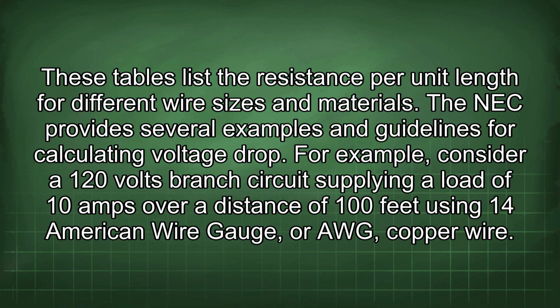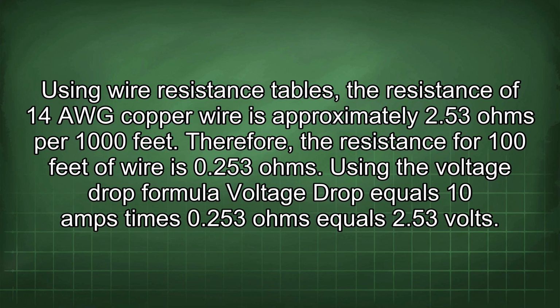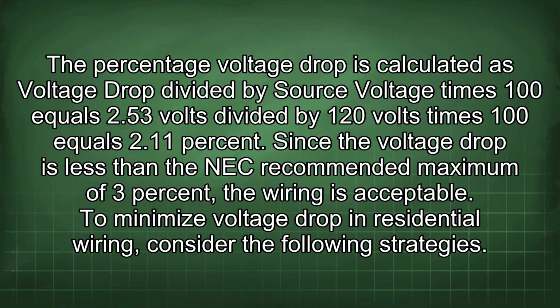For example, consider a 120 volt branch circuit supplying a load of 10 amps over a distance of 100 feet using 14 American Wire Gauge, or AWG, copper wire. Using wire resistance tables, the resistance of 14 AWG copper wire is approximately 2.53 ohms per 1000 feet. Therefore, the resistance for 100 feet of wire is 0.253 ohms. Using the voltage drop formula, voltage drop equals 10 amps times 0.253 ohms equals 2.53 volts. The percentage voltage drop is calculated as voltage drop divided by source voltage times 100, equals 2.53 volts divided by 120 volts times 100, equals 2.11%. Since the voltage drop is less than the NEC recommended maximum of 3%, the wiring is acceptable.